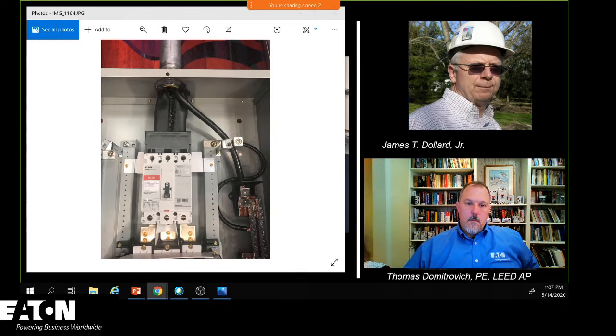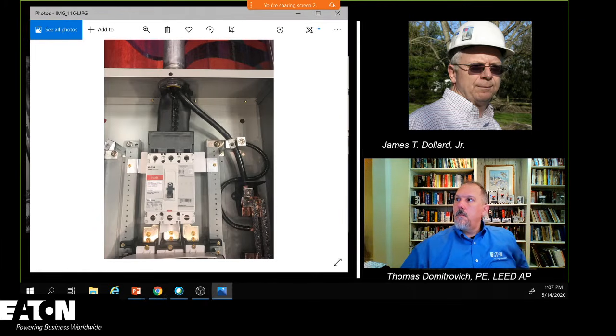I can tell you this, that requiring those barriers just like that was one of the greatest leaps forward that we've ever done in the National Electrical Code with respect to safety, because in service equipment, when somebody does come in contact with the line side, in all of the situations that I've seen, it occurred inadvertently. There was no intent to be in that area. Somebody was holding an equipment grounding conductor, for example, and they're going to land it, and it springs up and in. I mean, there's a lot of people that are in the graveyard today because just that happened. But what that does is significantly reduce the likelihood of an incident.